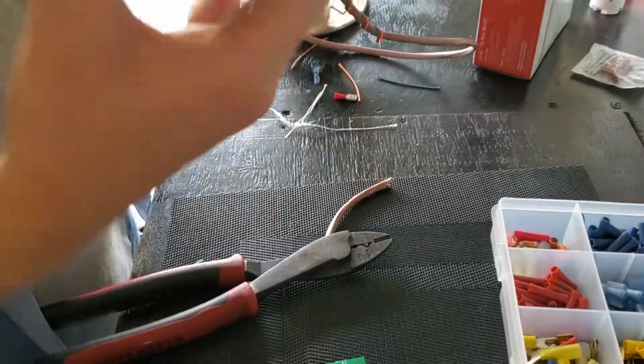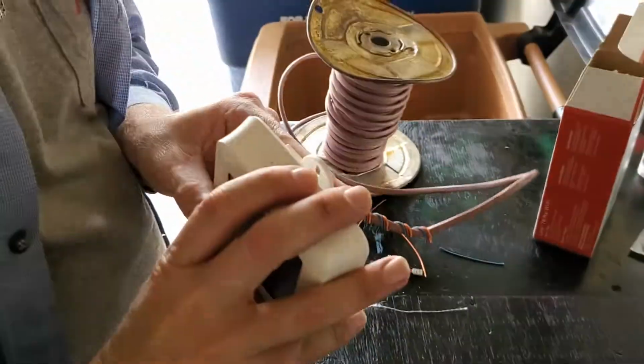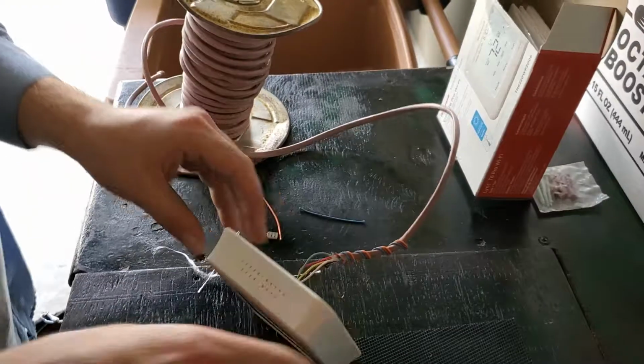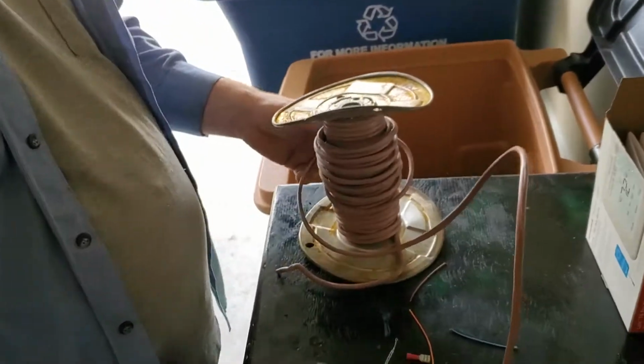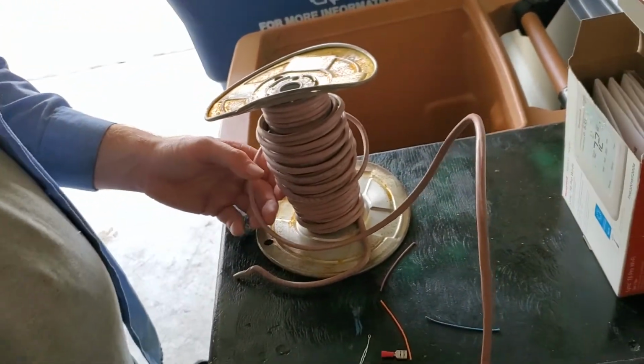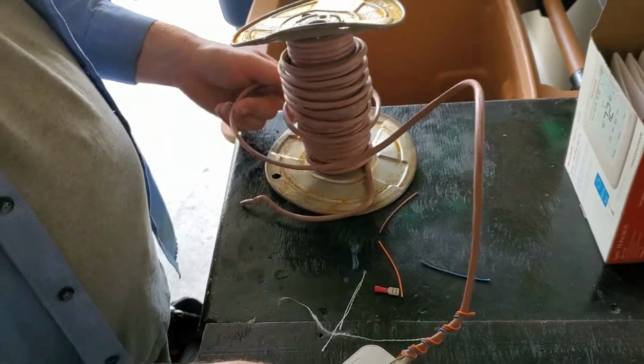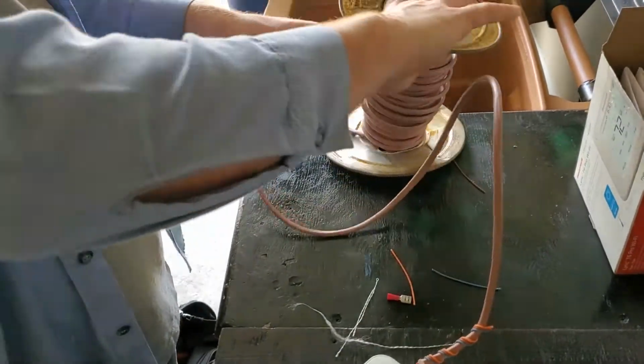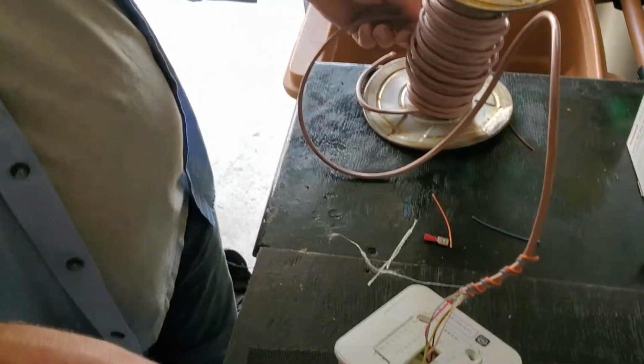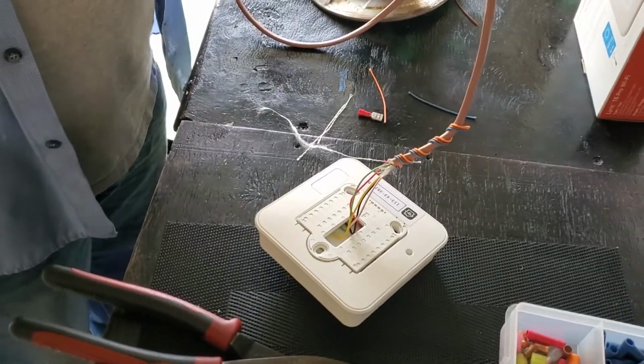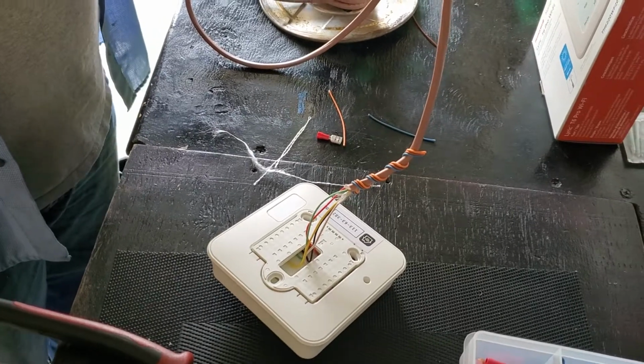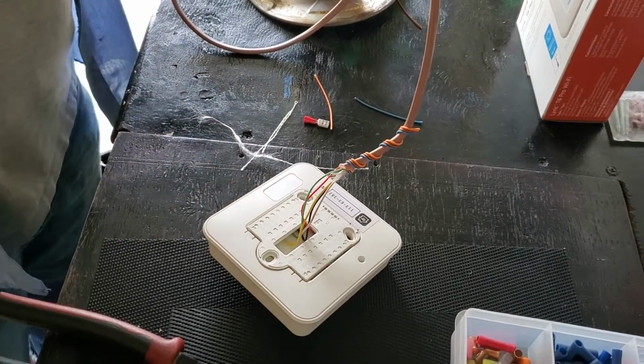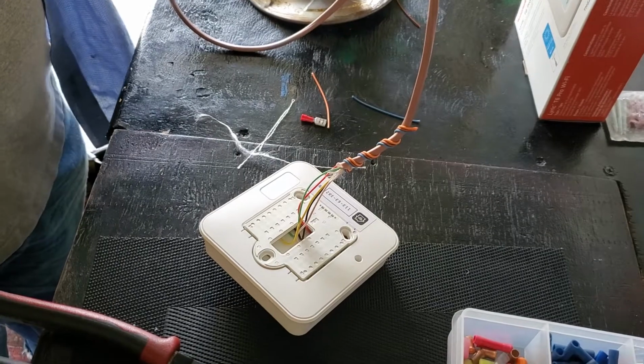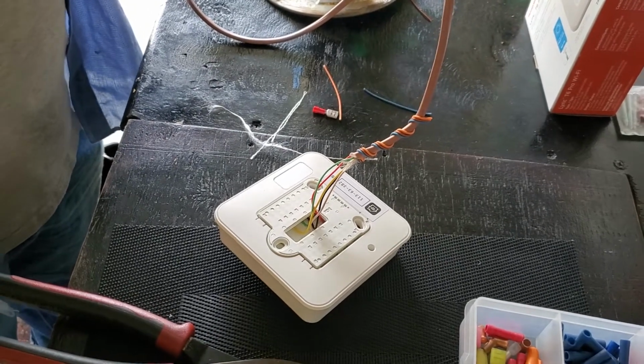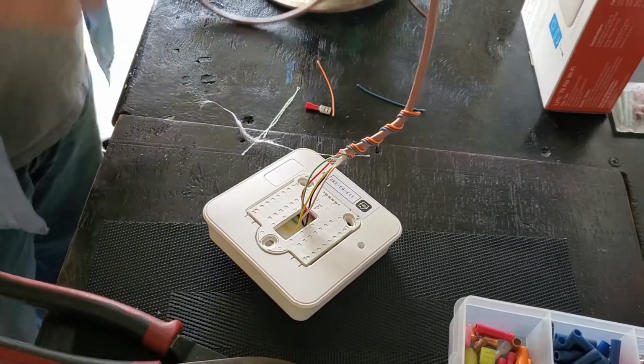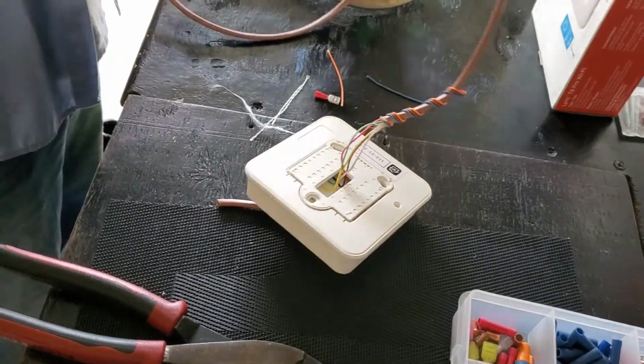So there's that, and there's your thermostat. This thermostat takes that 24-volt control signal, and it's got a bunch of micro relays on it and sensor inputs. What it's looking at is the temperature of your house, and whenever the temperature goes out of a certain range, it closes a micro relay, which sends 24 volts to a contactor inside the air handler. When the contactor closes, that energizes your fan and all the stages this thing goes through.